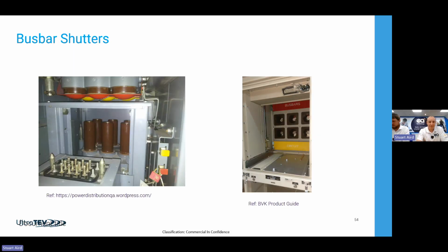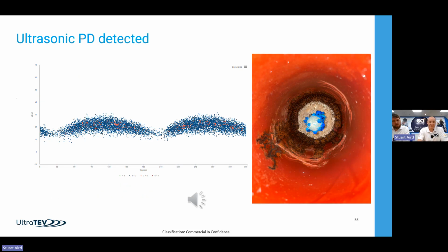So I've got a couple of examples and a picture on the next slide. So this was one that we detected in service. So it's a switchgear panel, switchgear lineup, and all the other ones were running, and this one had its breaker racked down. But literally just point your microphone into that little area and we could hear it clear as day. And it's actually on the circuit side, and you can listen to that sample as well. I think it's relatively loud.